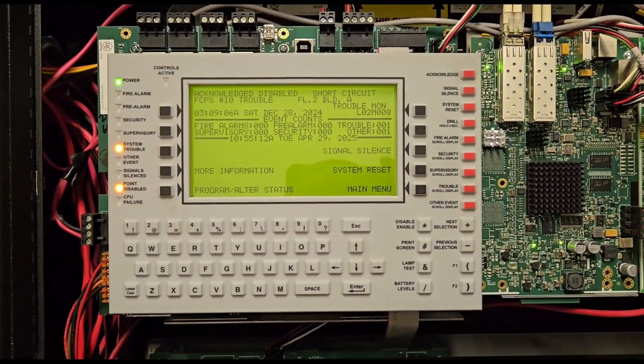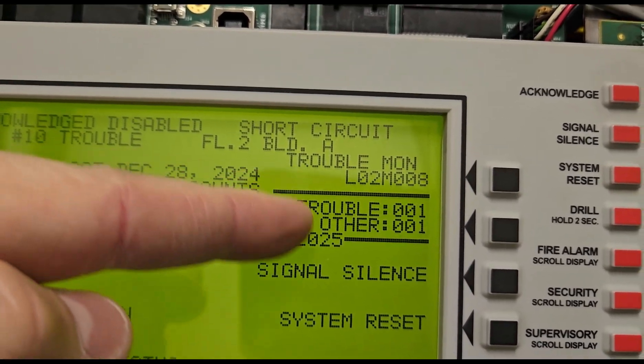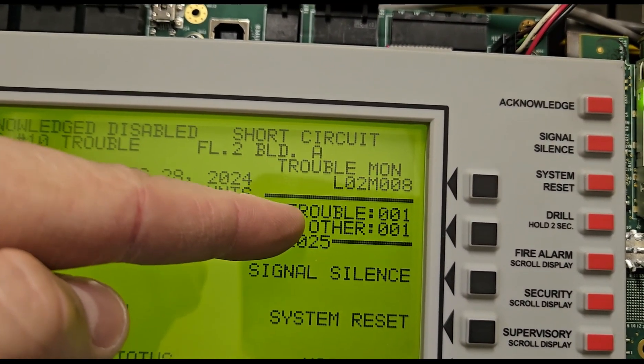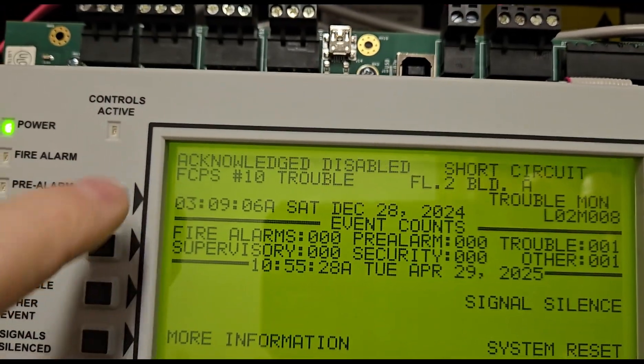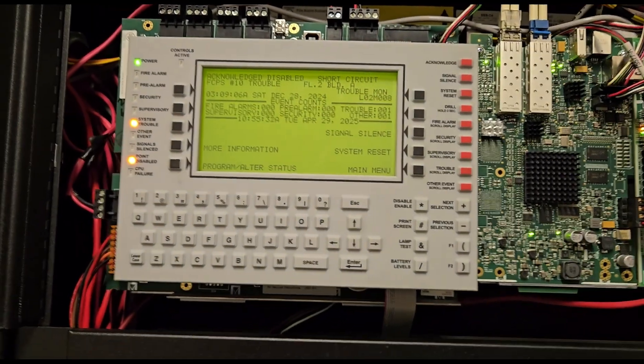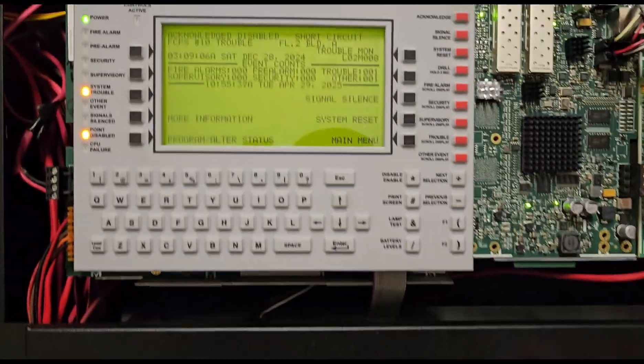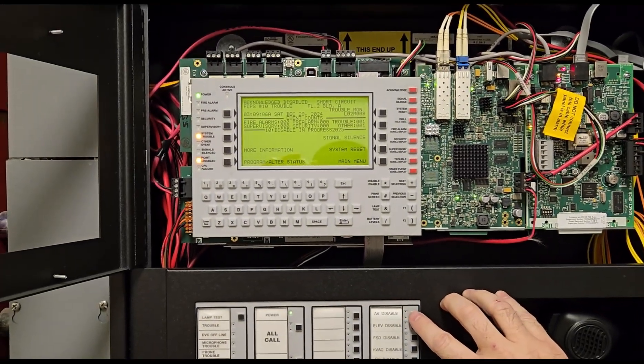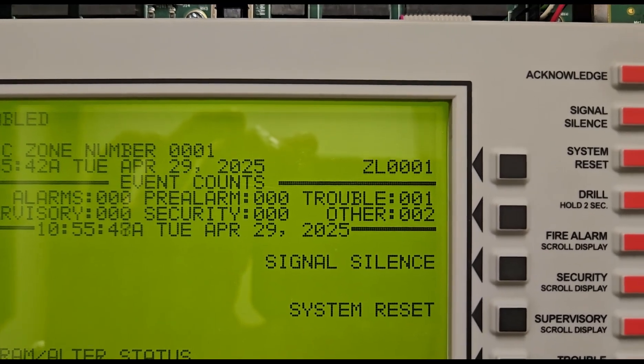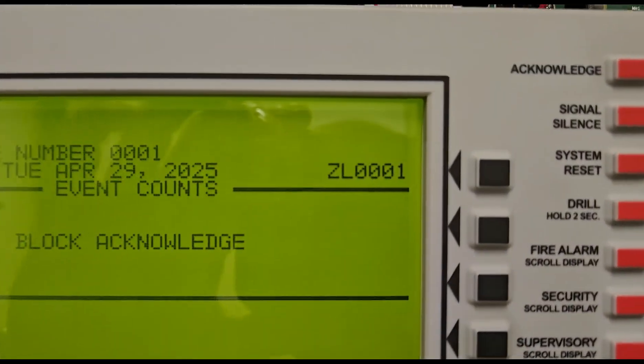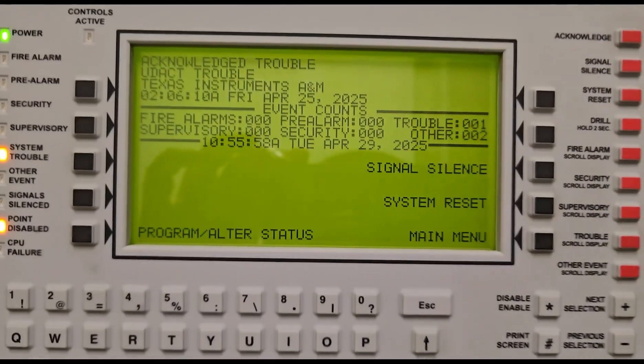Pay attention to the trouble and other counts here — typically when you disable something you'll get something under trouble or other. This one will come under 'other.' We're currently at zero zero one for both before we disable anything. We'll start with AV disable first. We get our trouble saying 'disable in progress' and we now have two. Let's hit acknowledge — now we have other two, so we went up by one.